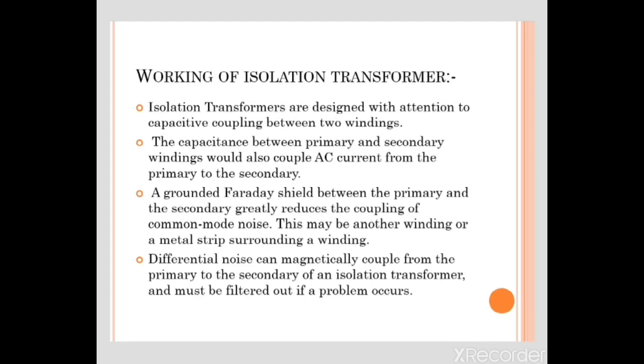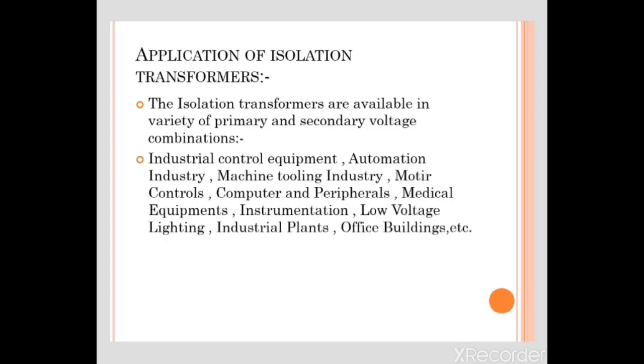Working of the isolation transformer. Isolation transformers are designed with attention to the capacitive coupling between the two windings. The capacitance between primary and secondary windings will also couple AC current from the primary to the secondary. Differential noise is magnetically coupled from the primary to the secondary, and isolation transformers must filter this out if a problem occurs.